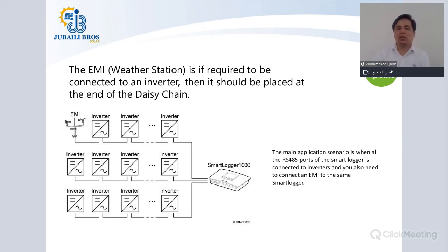So you can only install a weather station at the end of the daisy chain, not a power meter. People sometimes mix this up. They might think that they can also connect a power meter at the end of a daisy chain of solar inverters, but no. You can only install a weather station at the end of a daisy chain of solar inverters.